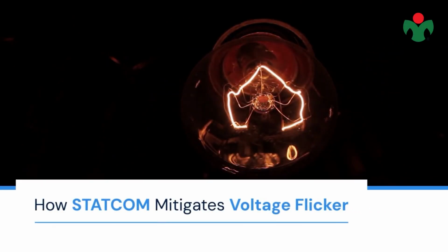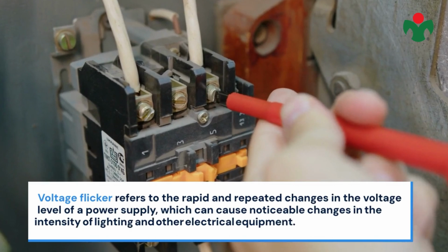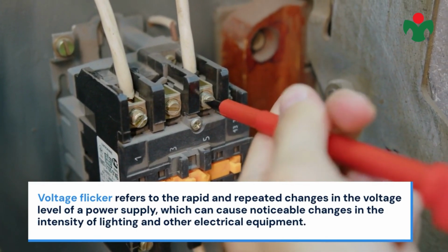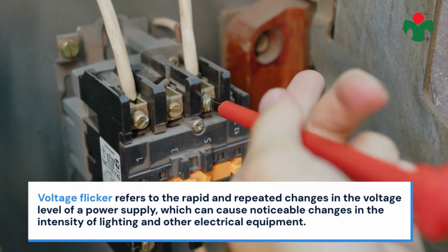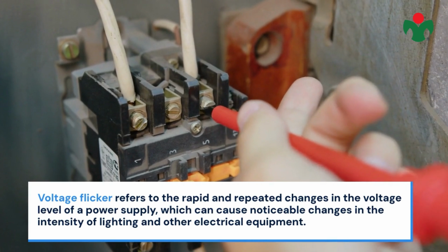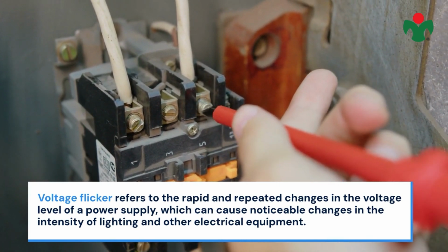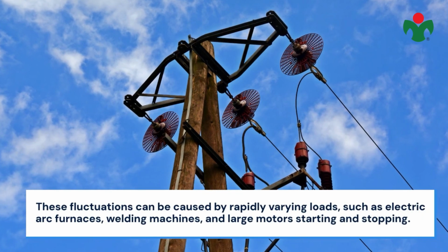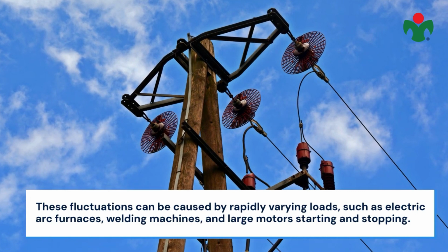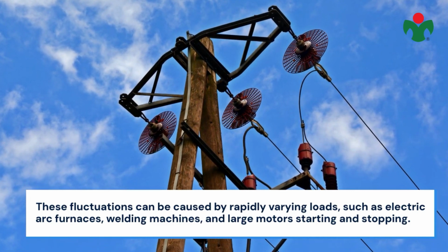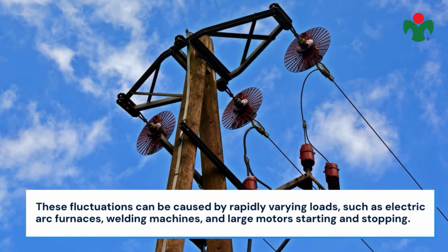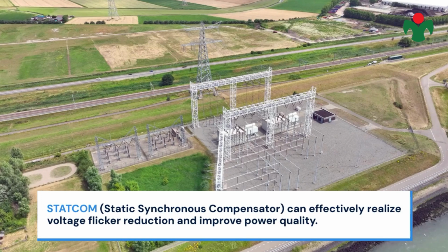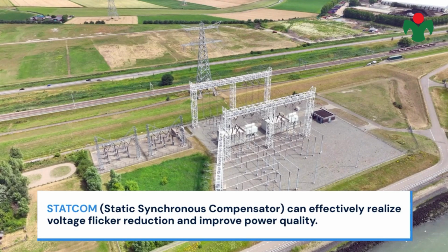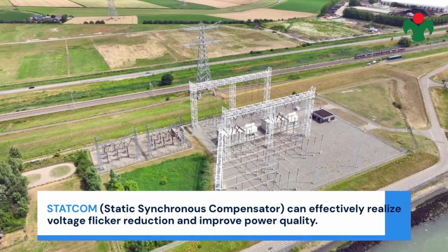How STATCOM mitigates voltage flicker. Voltage flicker refers to the rapid and repeated changes in the voltage level of a power supply, which can cause noticeable changes in the intensity of lighting and other electrical equipment. These fluctuations can be caused by rapidly varying loads, such as electric arc furnaces, welding machines, and large motors starting and stopping. STATCOM, static synchronous compensator, can effectively realize voltage flicker reduction and improve power quality.